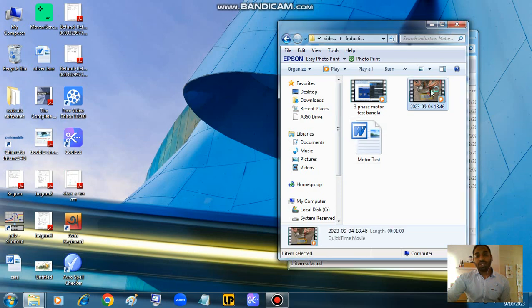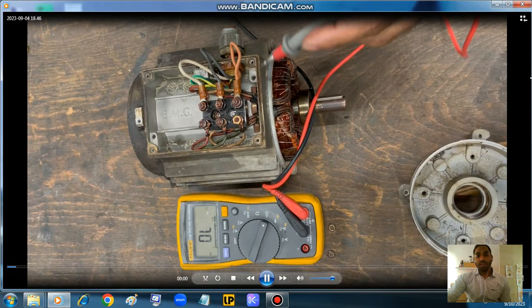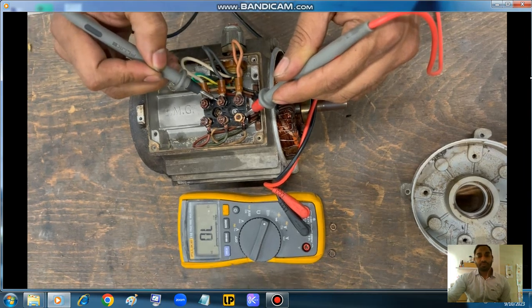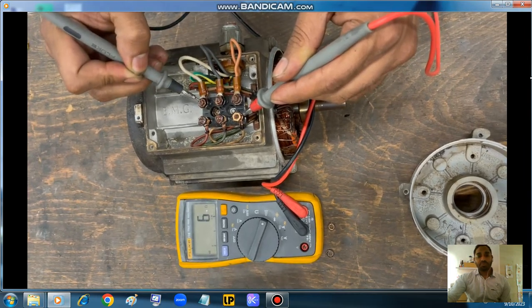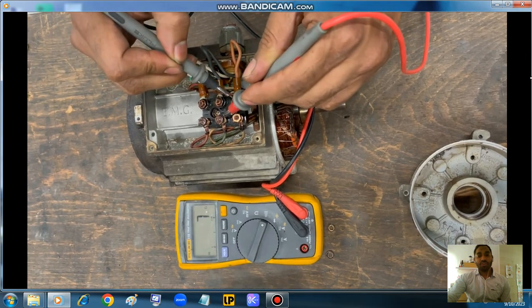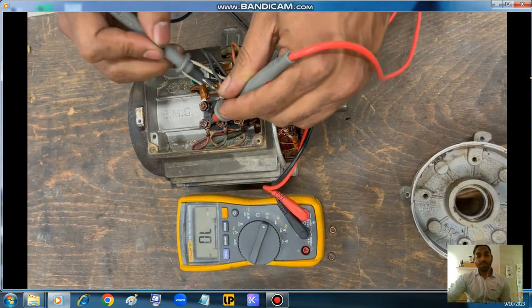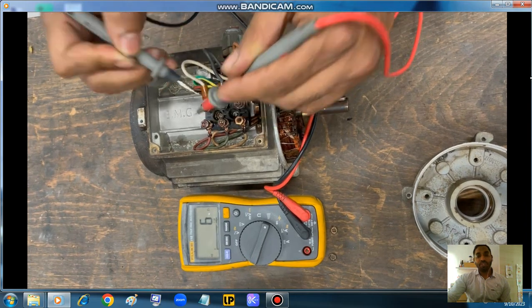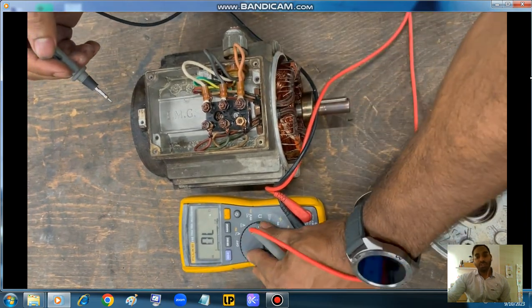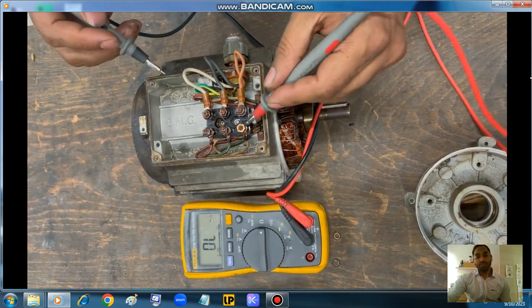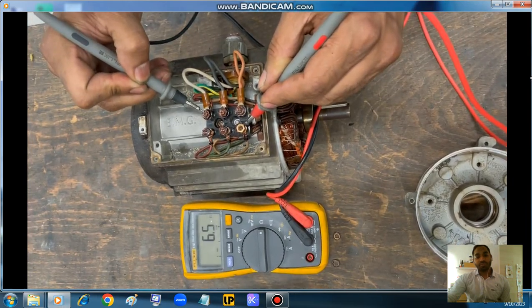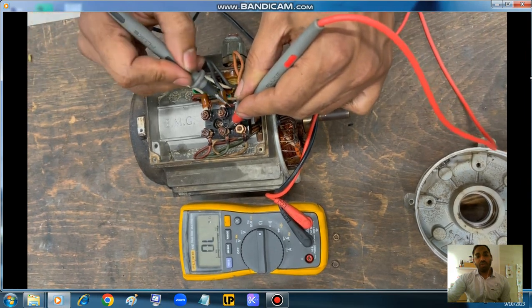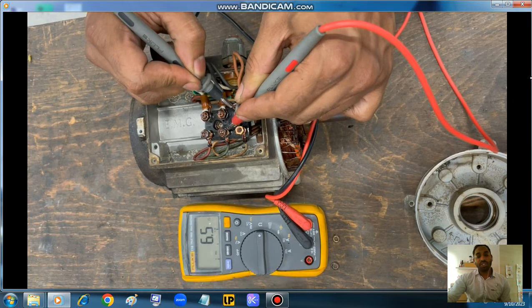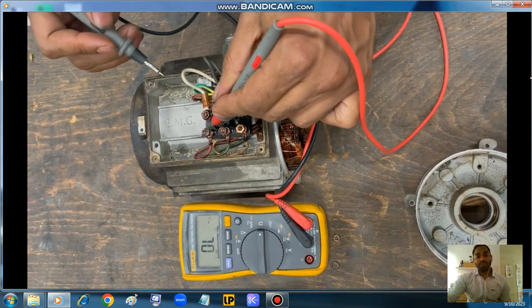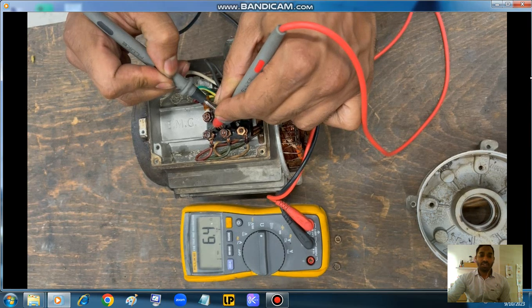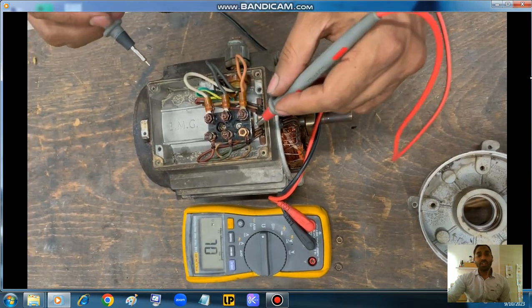Now we have a video here. Here we can see how to test. This is a continuity test. You can hear the beep sound, which means all the wires are okay, they are not broken inside. Now the resistance test, to check that the wires are not short circuited, not connected to each other. See, we get the same amount of resistance here also, which means the wires are not connected with each other.